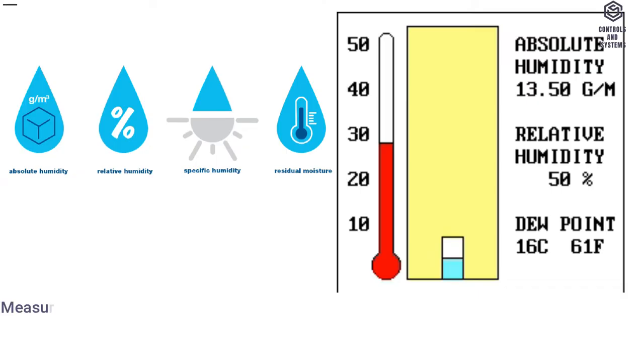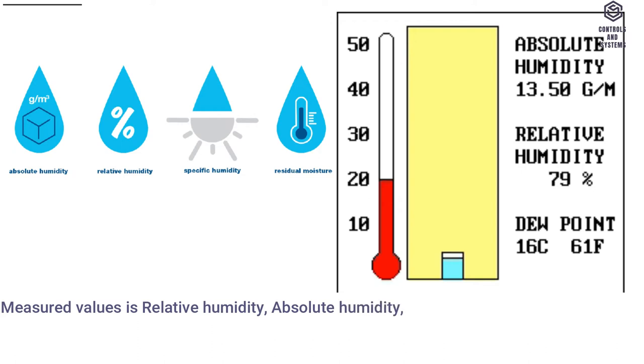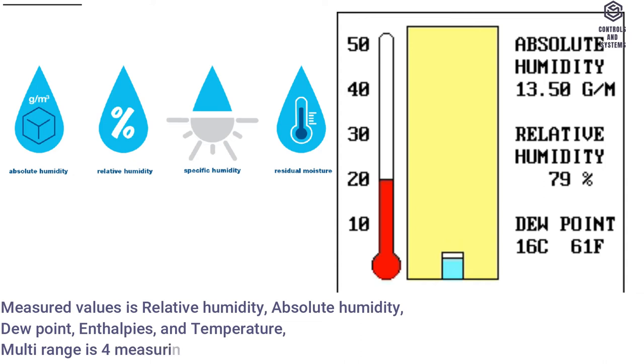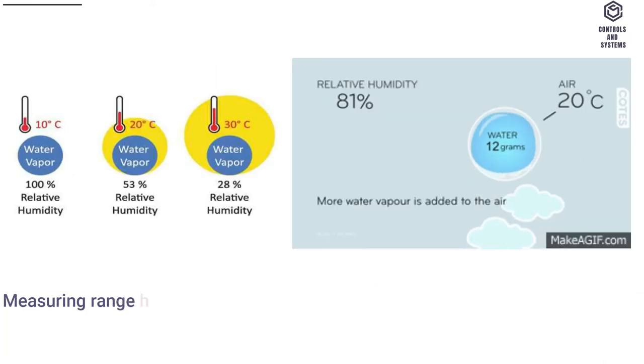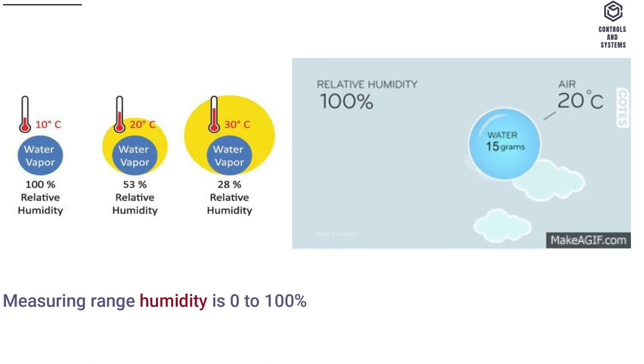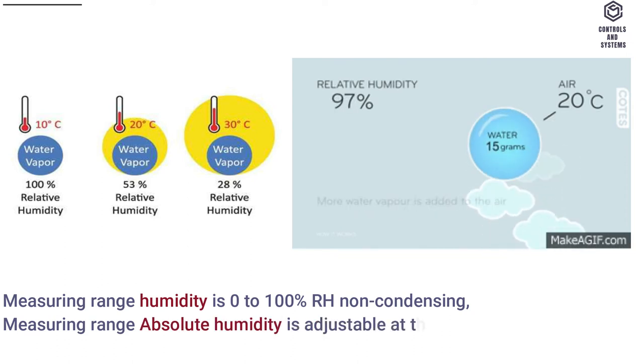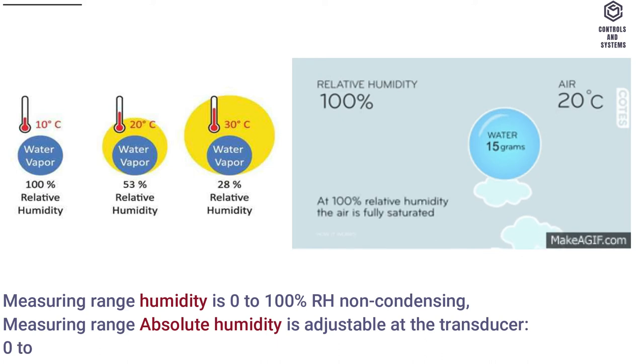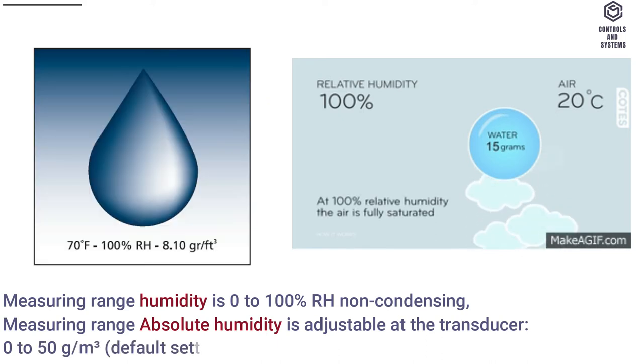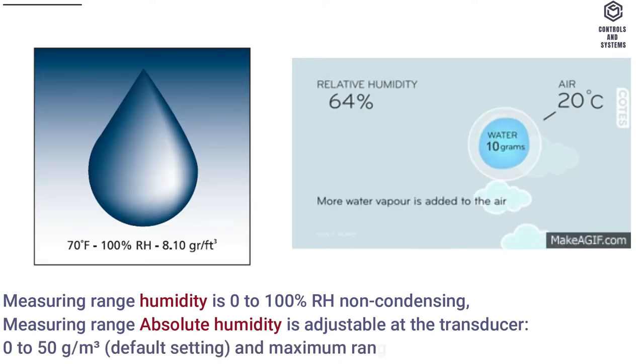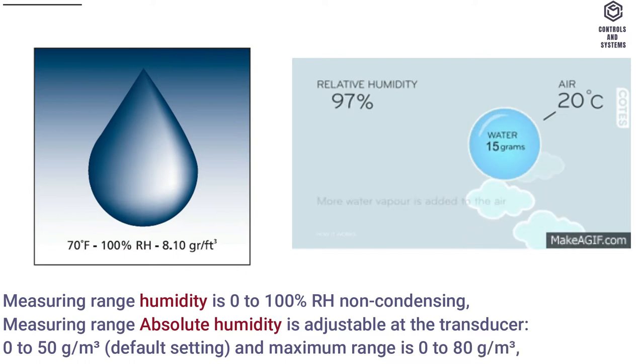Measuring Data: Measured values are relative humidity, absolute humidity, dew point, enthalpy, and temperature. Multi-range is 4 measuring ranges selectable. Measuring range humidity is 0 to 100% RH, non-condensing. Measuring range absolute humidity is adjustable at the transducer: 0 to 50 g/m³ default setting, and maximum range is 0 to 80 g/m³.